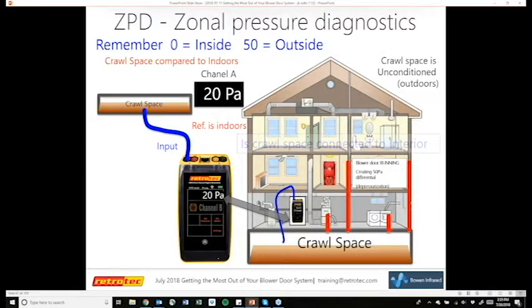And then the same for crawl space. Crawl space, sometimes it can be a little tricky to get something down there, kind of like with attics. If you have ducts in the floor, if it's an existing home, you can pull up the register. Sometimes you can get a gap between the supply boot and the floor to put a hose down there. Sometimes there's an access hatch to get into the crawl space. But if you don't have those two options, you can then run a hose outside and then come back into a crawl space vent or through the crawl space door.